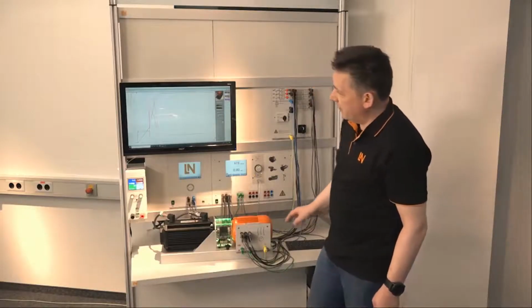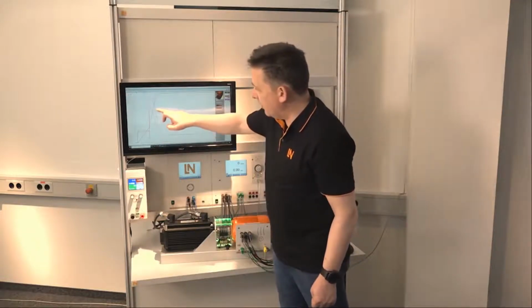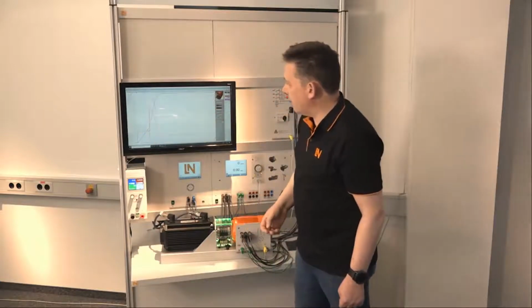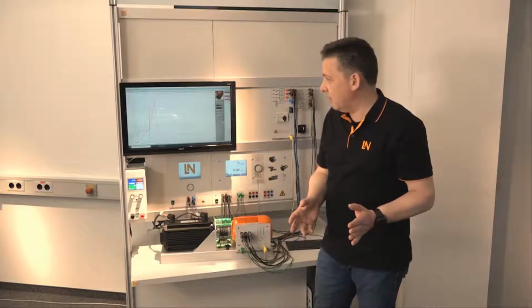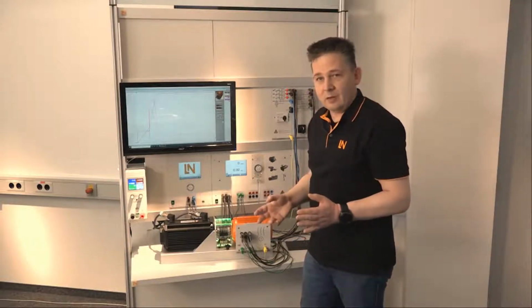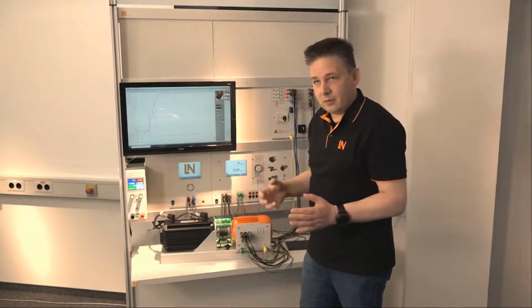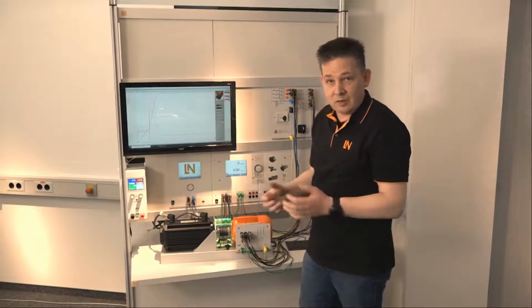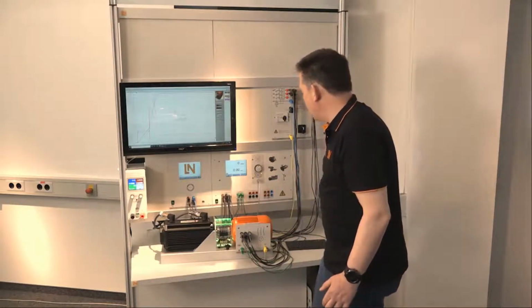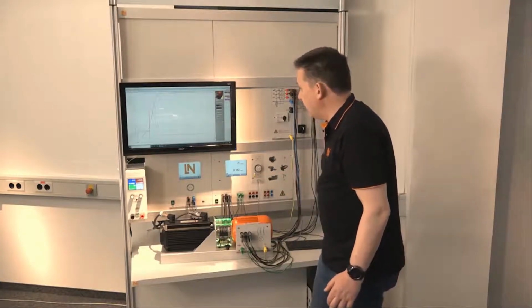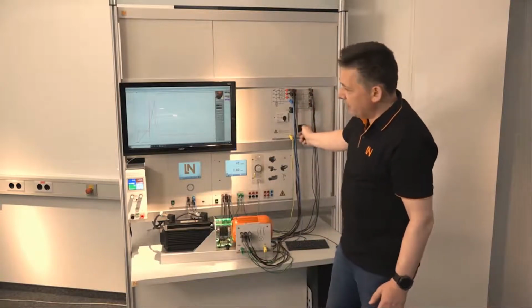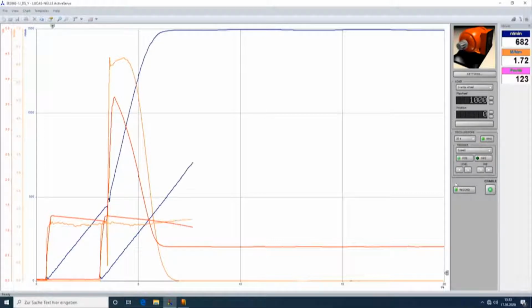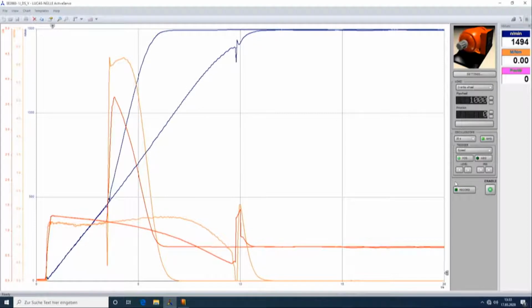press stop. The challenge now is to reduce this inrush current up to, I will say, 1.5 amperes. So the student has to find the right time, the correct value to do the switching, to understand what happens. This knowledge can be transferred later to the industry. So what will we do? We do the same experiment again, press record again. Now I start in Y circuit and wait until the right point is given to switch to delta connection. And now we see we have reduced this high inrush current to a small value.